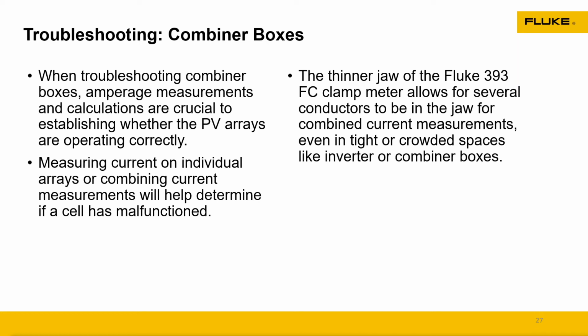Also too, at your combiner box, the technicians are able to take multiple wires in it and see in a grouping, do all of my amperages look equal? Again, if the system was designed correctly, the irradiance is correct on all of the panels, I should have an equal amount of voltage and current coming off of each string, or relatively close to it. This is a good way to go to your combiner box and do some analysis. The combiner box is going to have your fuses, where that's where you're going to be troubleshooting and seeing what's happening with the system.